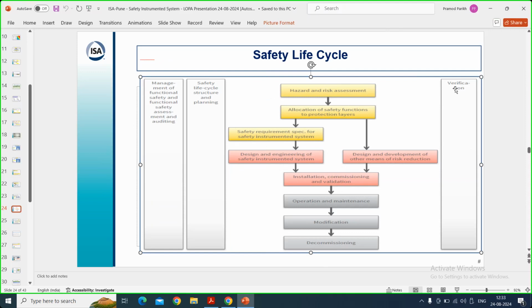Whereas verification is to be done at each and every phase of the safety life cycle. So verification for each and every phase, whereas validation is only for checking whether the system which is designed and being commissioned is meeting the safety requirement specification or not. I hope I'm clear.